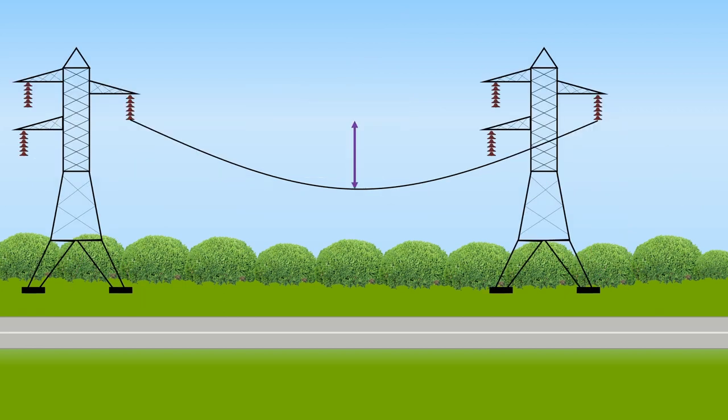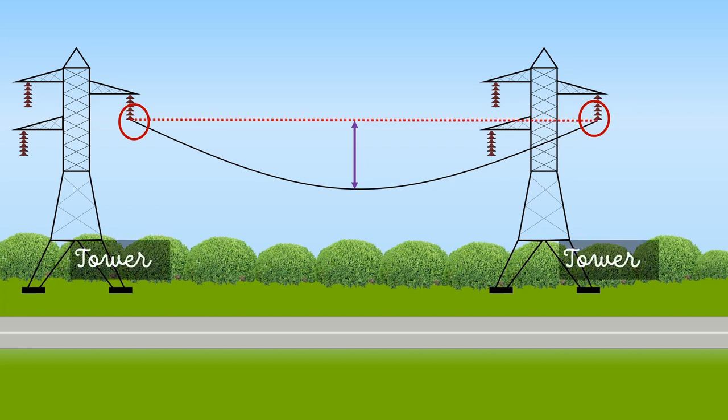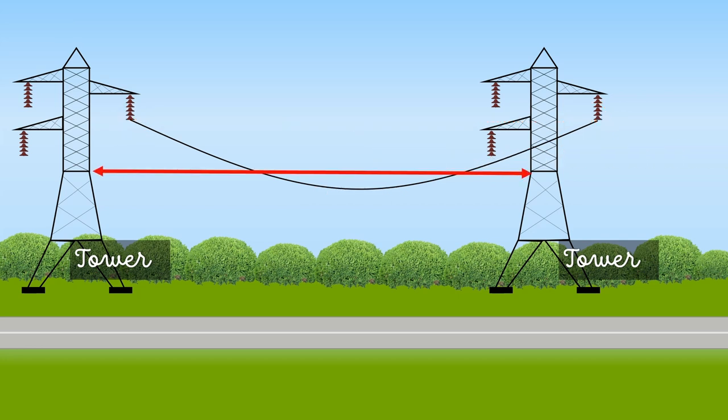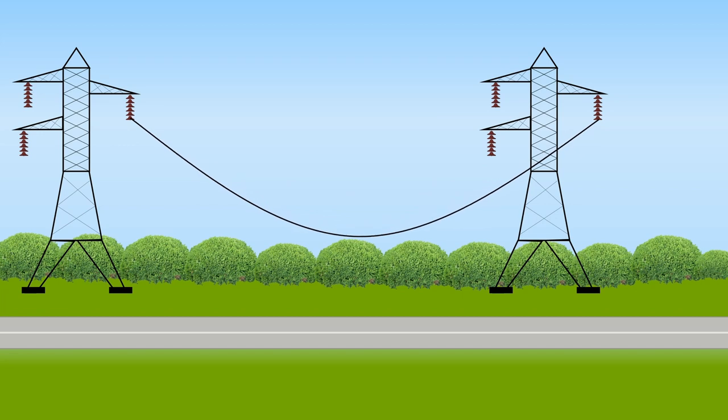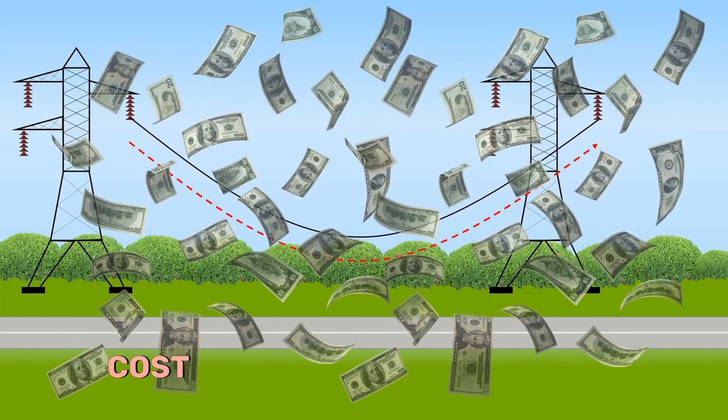The vertical distance between the highest point of the electrical pole or tower where the conductor is connected and the lowest point of the conductor is known as the sag. The horizontal distance between two towers is called the span. The length of the conductor used will be more if the sag is more. This obviously increases the cost.